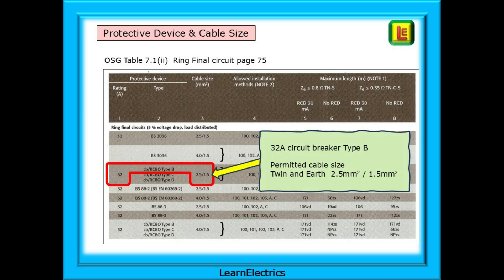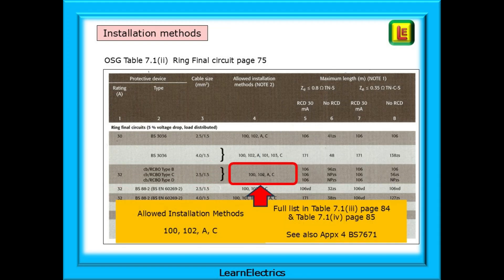Now find the correct protective device on page 75. We have a 32-amp circuit breaker, or CB, Type B, and the table tells us to use twin and earth with 2.5 square millimetre conductors and 1.5 square millimetre earth, or CPC. On to column 4 - what are the allowed installation methods for this circuit, with this breaker, with this size cable?